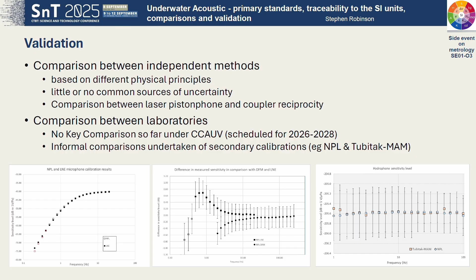I just wanted to say a little bit before I finish on secondary calibration methods in a small chamber. So essentially here, the principle is much easier. You basically just expose the 2 hydrophones, the reference one already calibrated by a primary method and the device under test to the same sound pressure or oscillating pressure in the case of pressure calibrations. And then you measure the ratio of the voltages and you can calculate easily the sensitivity.